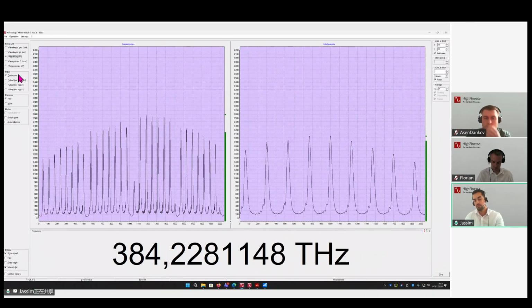Underneath it, as we have briefly mentioned, you could use the wavelength meter to measure continuous or pulsed lasers. And with pulsed lasers, we have a certain pixel in the CCD array that will wait for a certain intensity value, and on the rising edge of that value, the measurement will be enabled and you will be able to see your measurement.